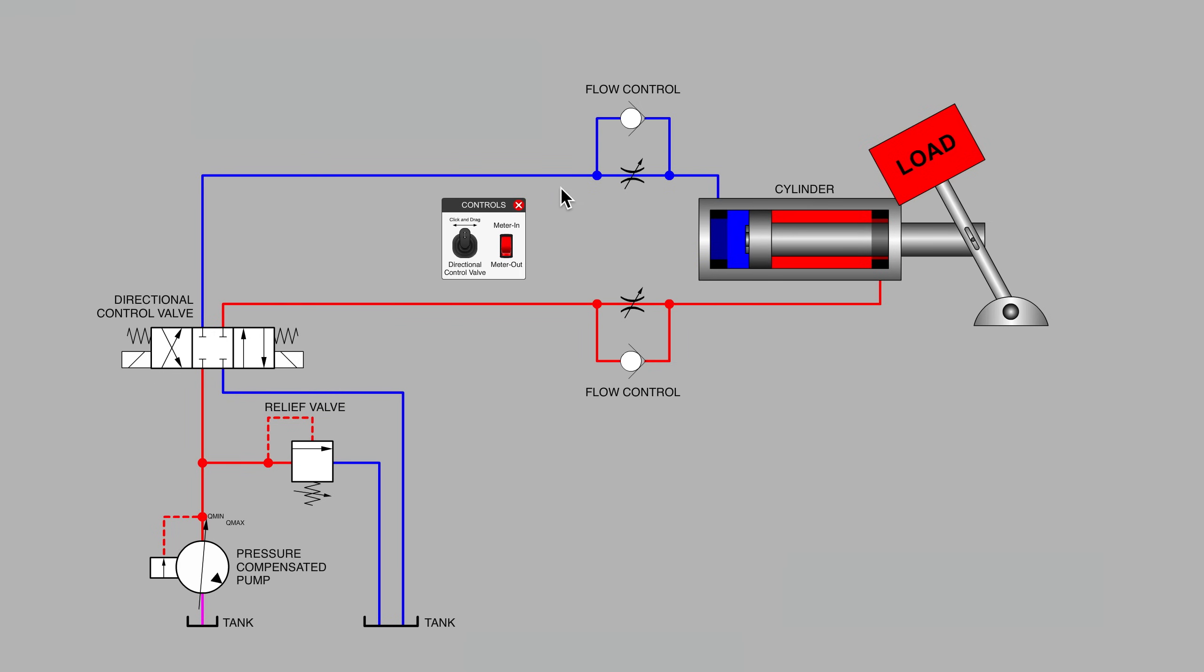So the way we have this particular flow control plumbed in to the blind end of the cylinder, we are currently set up for a form of flow controlling called meter in. And the word meter in or the word meter out is not a reference to which direction the cylinder is traveling, but rather a reference to whether or not we are controlling the rate of flow as fluid enters the cylinder or as fluid is leaving the cylinder. So in this case, we are set up to meter the fluid as it enters the blind end of the cylinder.